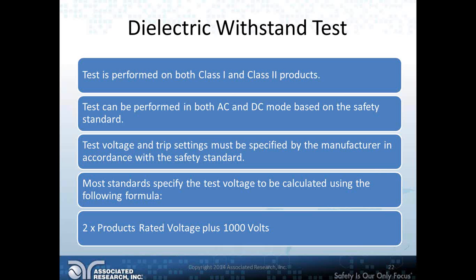Test voltage and trip settings must be specified by the manufacturer in accordance with the relevant safety standard. As a rule of thumb, most standards specify the high pot test voltage using the formula: twice the product's rated voltage plus 1,000 volts. So for a 120-volt product, the high pot test voltage would be 1,240 volts.